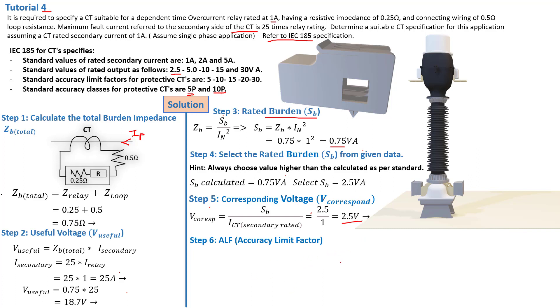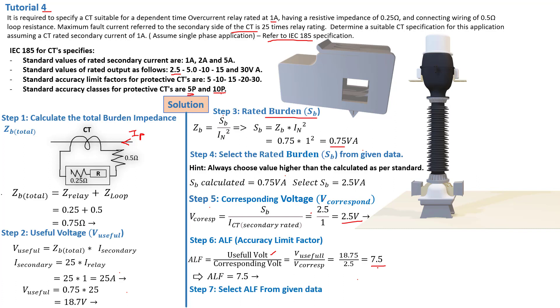Step number six: the accuracy limit factor. The accuracy limit factor is given by ALF equals the useful voltage divided by the corresponding voltage: 18.75 divided by 2.5. You can now see why we calculated the useful voltage — it is used to calculate the ALF, which determines how much current can pass through the CT primary before saturation. We find an ALF of 7.5, which is not a standard value, so we must select the next higher standard value: ALF equals 10.